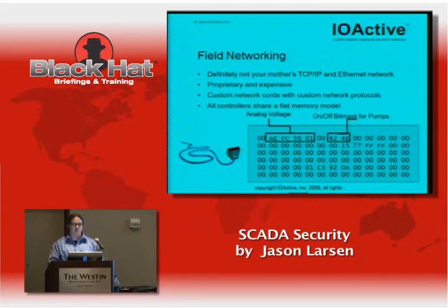And this is what you cable your PLCs together with. So inside the PLC is a flat memory model, and all the PLCs share a flat memory model. So when you slap in a new card that reads some analog points off of a speed or sets some digital points, you know, pumps, valves, whatever, then those are actually mapped into the shared memory segment. And in most of these protocols, you actually have to know the mapping in order to make sense of it, because the protocol itself only does bulk reads and writes from memory.